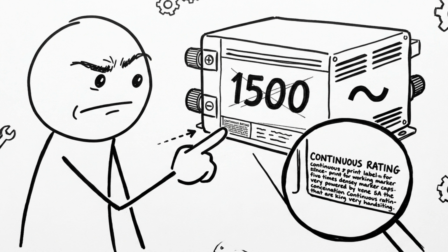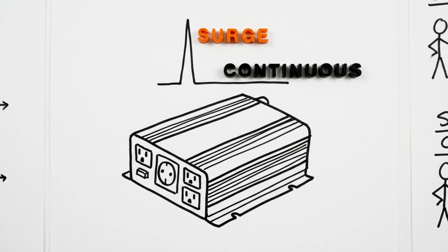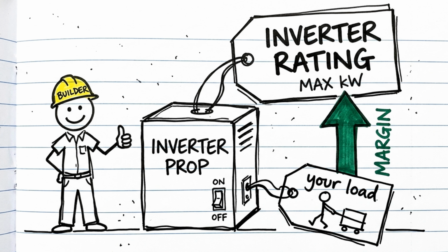The inverter converts your battery's DC into household AC, and the one spec that matters is its continuous power rating, not the number on the box in bold, the number in the fine print. Inverters can briefly exceed that rating for a few seconds to handle a motor starting up, sometimes more than double the running wattage, but that's a surge allowance, not a sizing number. A sensible margin is to pick an inverter rated meaningfully above your actual connected load, not exactly at it, including headroom for motor starting surges.